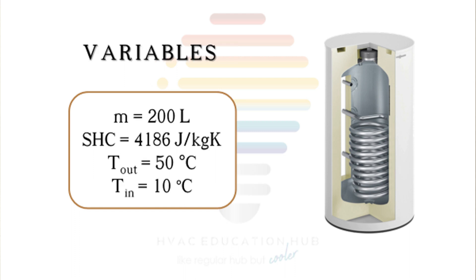This is the mass of our tank. We have specific heat capacity of water, which is 4186 joules per kilogram per kelvin. We want target temperature in tank of 50 degrees Celsius, and our main water supply temperature is 10 degrees Celsius. We have all data to calculate how much energy we need.